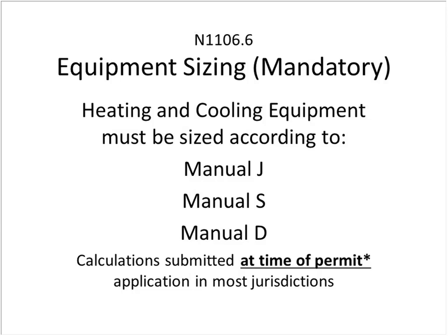A lot of jurisdictions are looking for this information, and quite oftentimes we're seeing it now showing up on the construction drawings for the project. And so it'll not only have these Manual S selection numbers on the drawings, but they'll also have the thermal envelope values that are being installed on those drawings too, so that they have all that information in one place. This is a new requirement. It's been required for a long time that you have the equipment properly sized, but now they actually spell it out. And in some jurisdictions, they want it up front. Other ones, they have to have it before you get a certificate of occupancy.